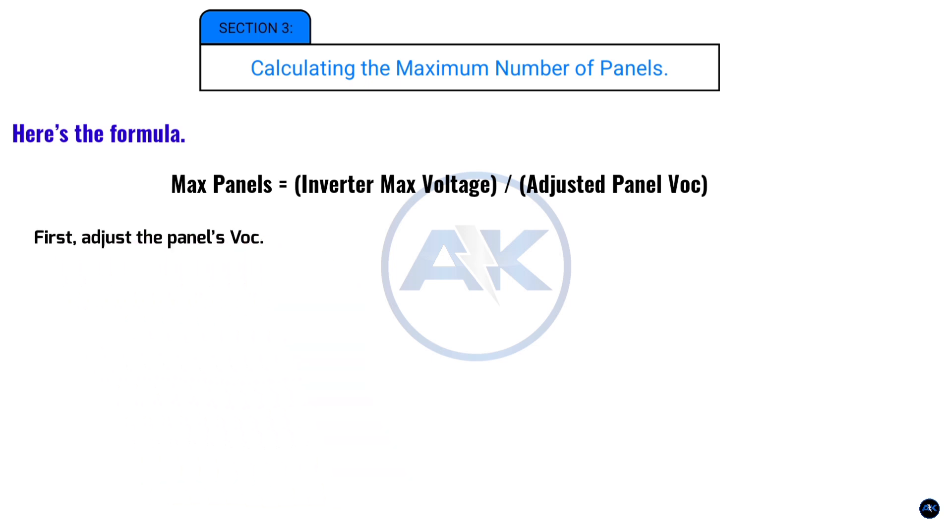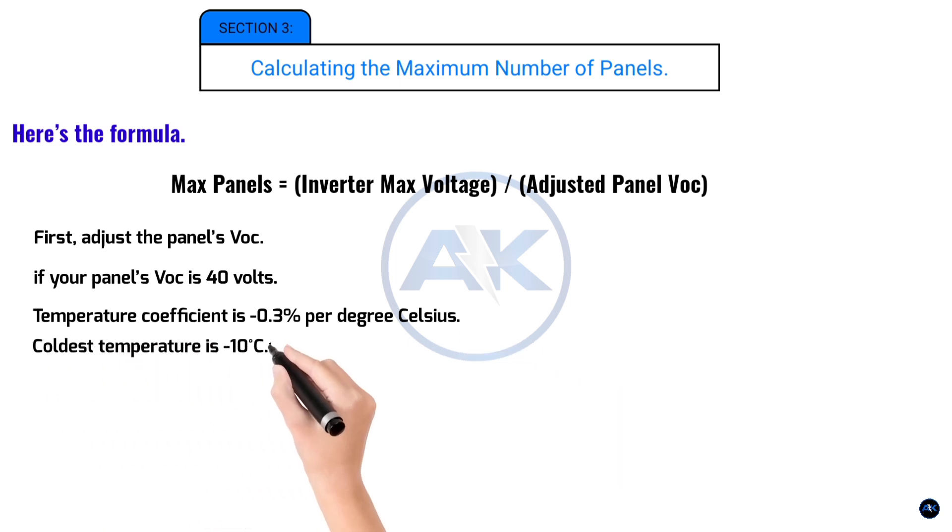First, adjust the panel's VOC for the coldest temperature in your area. For example, if your panel's VOC is 40 volts and the temperature coefficient is negative 0.3% per degree Celsius and the coldest temperature is minus 10 degrees Celsius, the adjusted VOC would be higher.